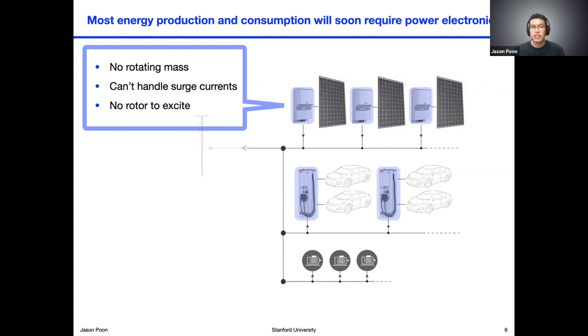These power electronics are quite unique in and of themselves, because unlike synchronous generators, they do not have rotating mass. They also cannot handle very large surge currents — a power converter can only be pushed to about 2x of its rated current before something bad happens. And similarly, there's nothing rotating, so there's no concept of a rotor that can be excited to provide reactive power. These are fundamentally different devices than synchronous generators.